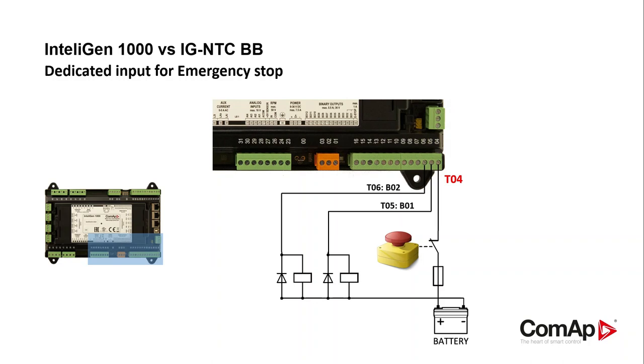If for some reason there is an absence of voltage in the T04 terminal assigned to the emergency stop, then the E-stop alarm will be activated in the controller and at the same time we will be internally opening the power supply to outputs 1 and 2, starter and fuel solenoid, which will deactivate them.